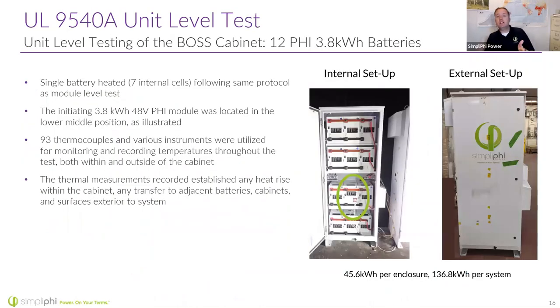After doing it on the module level, we moved up to the unit level testing. Inside that battery cabinet, we took the battery module and put it probably in the worst place you could think of - sandwiched between two adjacent batteries on a lower level shelf. So if this battery were to start flaming, it would cause these adjacent batteries to propagate, and potentially the upper batteries as well. We put it down in the lower middle position as illustrated.